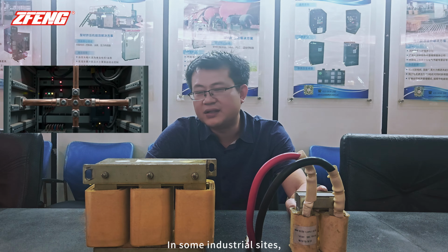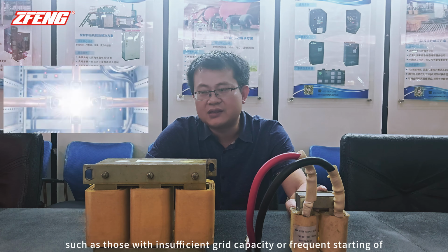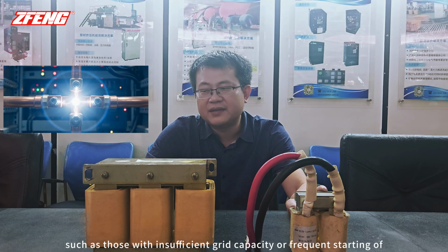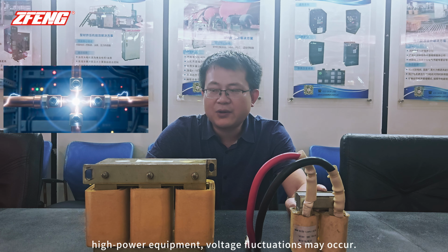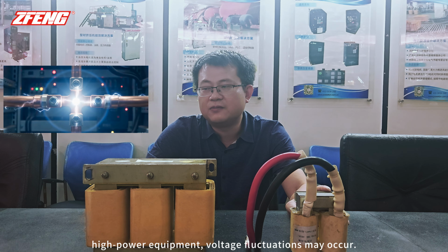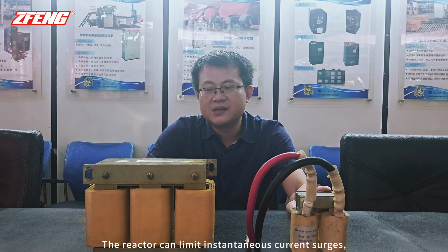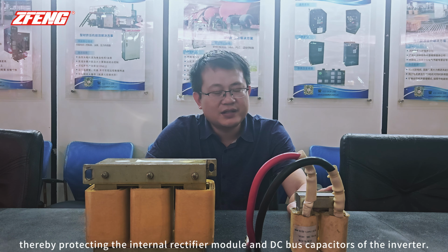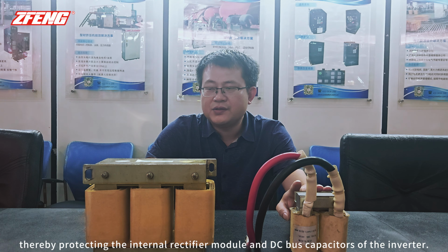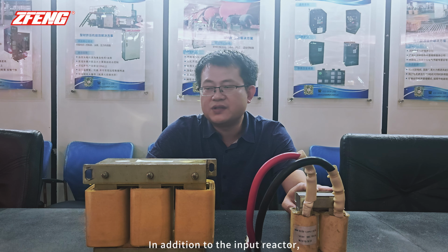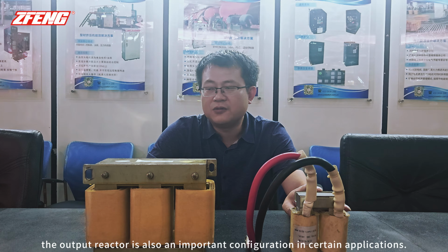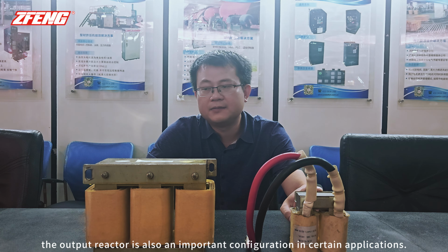In some industrial sites, such as those with insufficient grid capacity or frequent starting of high-power equipment, voltage fluctuations may occur. The reactor can limit instantaneous current surges, protecting the internal rectifier module and DC bus capacitor of the inverter. In addition to the input reactor, the output reactor is also an important configuration in certain applications.